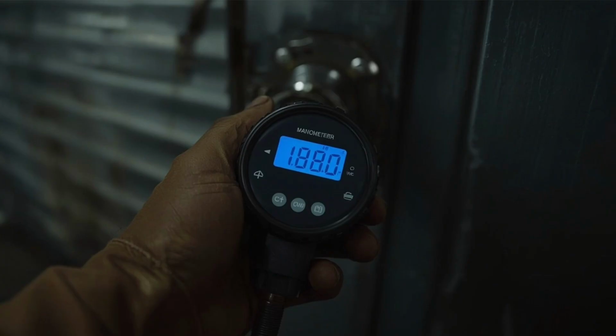With exhaust systems offline, the only significant pressure relief occurred through the building's revolving door assemblies, which maintained a small but continuous leakage area, and through gap tolerances around service doors in back-of-house corridors. Building automation logs recorded that static pressure in the main supply ductwork serving this zone reached 4.8 inches water column, well above the 2.5-inch design maximum, causing audible resonance in sheet metal ductwork spans and triggering high static pressure alarms that were logged but not acted upon by the automated control sequence.